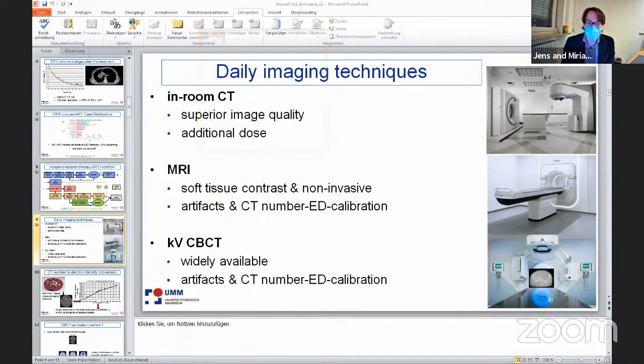The same thing counts for the last imaging device we have here, which would be the normal cone beam CT mounted to a linear accelerator. Good news is it's relatively cheap compared to the other techniques. It's widely available. You can buy it from all major Linac vendors. However, we also have the problem that these cone beam CTs are by nature cone beams, and a regular CT is a fan beam CT.